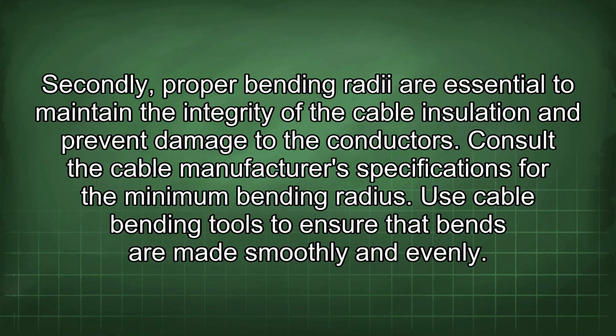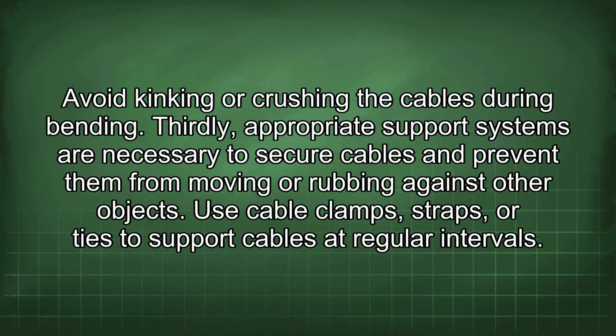Consult the cable manufacturer's specifications for the minimum bending radius. Use cable bending tools to ensure that bends are made smoothly and evenly. Avoid kinking or crushing the cables during bending. Thirdly, appropriate support systems are necessary to secure cables and prevent them from moving or rubbing against other objects.